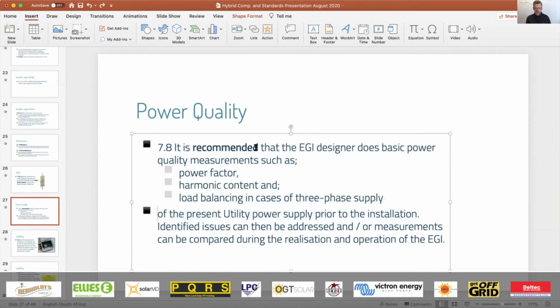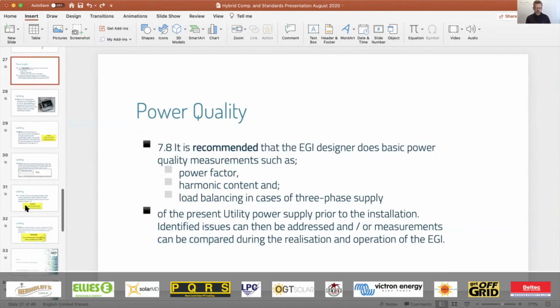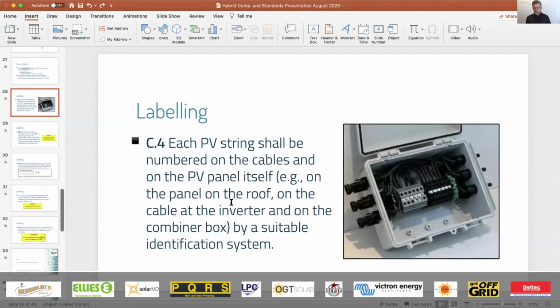So, such as power factor, harmonic, load balancing of the present utility power supply prior to the installation. This is to be done so that you can identify issues and then address them, and then even compare them after the installation. This is just what I would consider to be good practice. So it's just something that you've got to do in any case. I just see that it's being built into the standard.